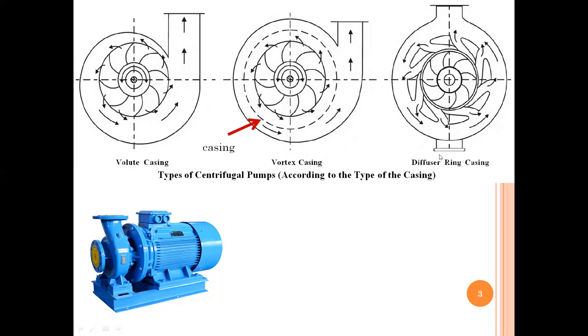Coming to the third type: casing with guide blade angles, also called diffuser ring casing. As water comes out of the central portion of the impeller, it passes through guide vanes which guide the water to flow upward in a regular pattern. Since it guides the flow after the impeller, it has a better efficiency. It has two names: diffuser ring casing, and casing with guide vanes. So the three types of casing are: volute casing, vortex casing, and diffuser ring casing.